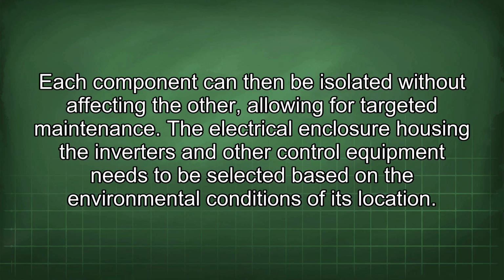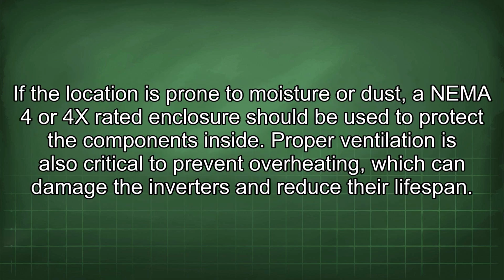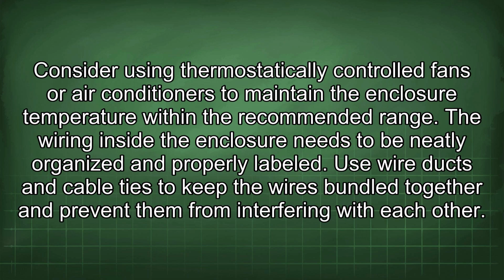The electrical enclosure housing the inverters and other control equipment needs to be selected based on the environmental conditions of its location. If the location is prone to moisture or dust, a NEMA 4 or 4X rated enclosure should be used to protect the components inside. Proper ventilation is also critical to prevent overheating, which can damage the inverters and reduce their lifespan. Consider using thermostatically controlled fans or air conditioners to maintain the enclosure temperature within the recommended range.